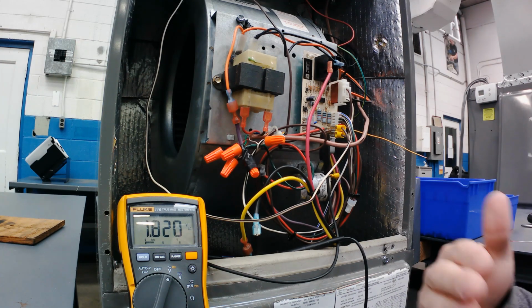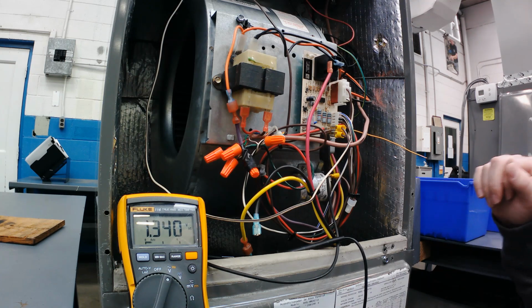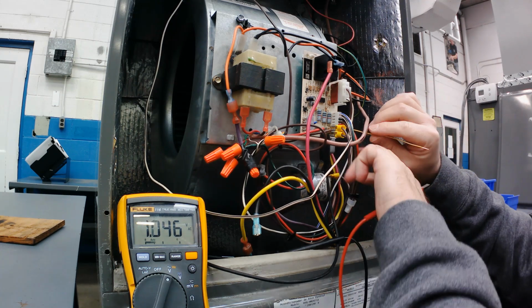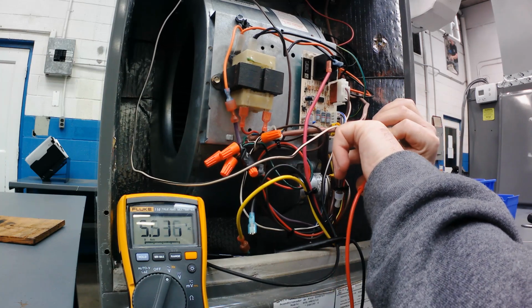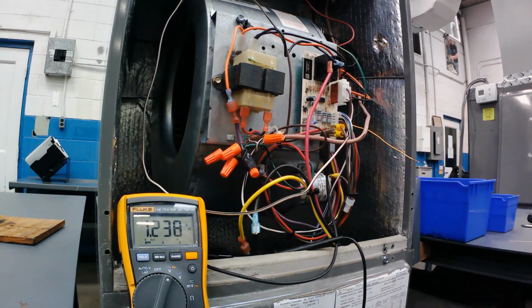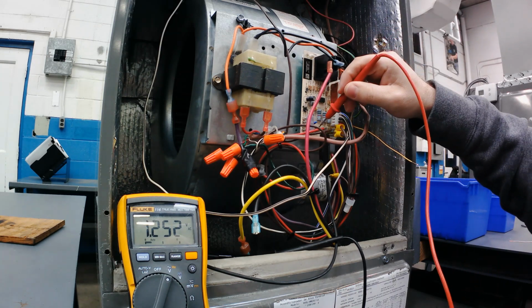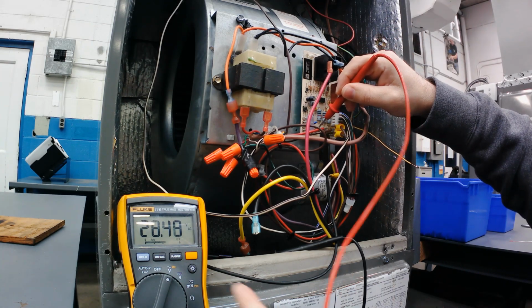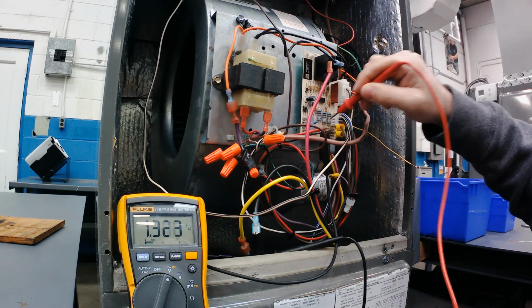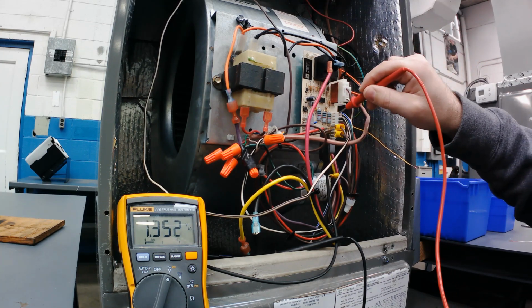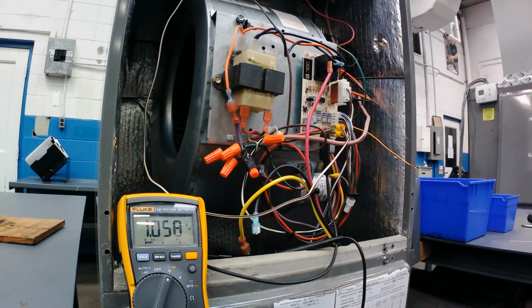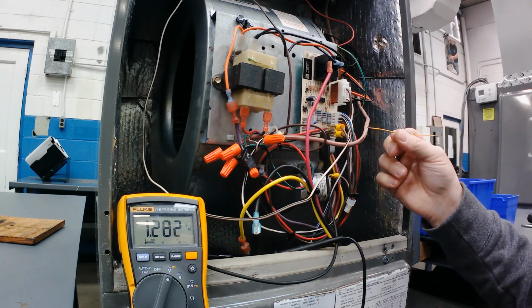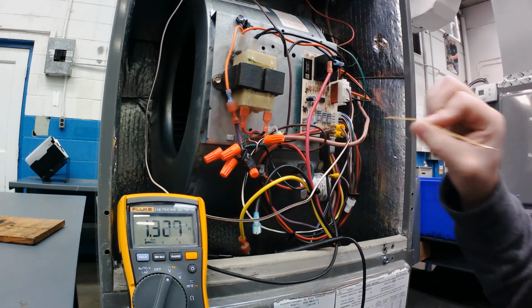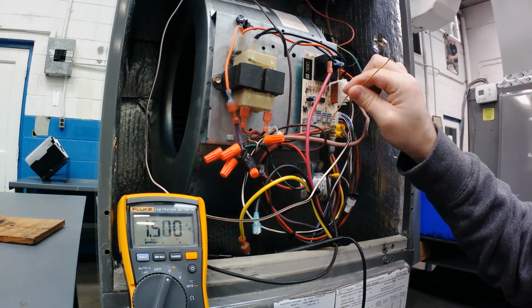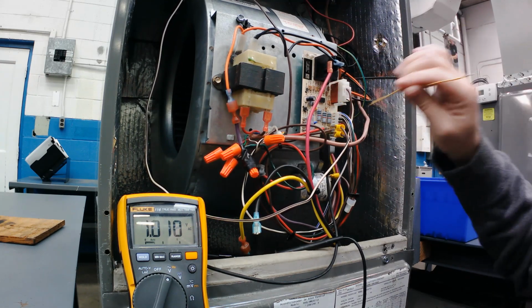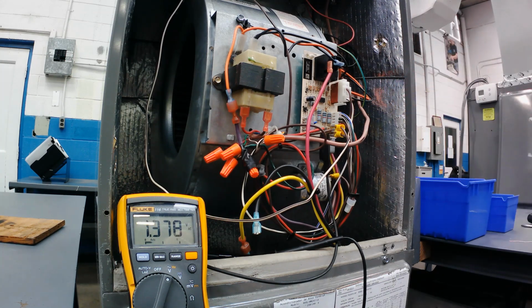Now likewise, that's one half of power to the thermostat. If you wanted to see if the common was good, I could move that wire up to the common terminal, and I could check it against the R. Okay, so I know I've got 28 volts here. I've got a good R circuit through the board, and I've got a good common back. All right, and that makes things easy. So a little piece of thermostat wire, an alligator clip. When I'm checking 24 volts, I never move it off of that transformer common, because that is the end of the circuit. That is my other side of power.